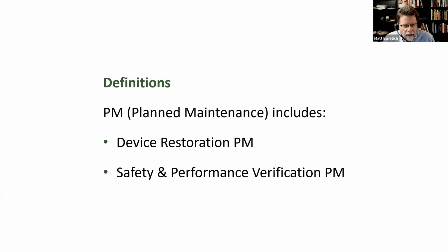There are two kinds of PM, and this is not my work; people like Malcolm Ridgway and others have been careful to distinguish these. There's device restoration PM, and that is things we do to get the device back into its good condition. We restore it to good function and safety. To me, that's true preventive maintenance, in the sense that if you fix things up, they are going to break less often. If you replace the battery before it goes bad, it won't fail when it's being used on a patient. So that's very important work.